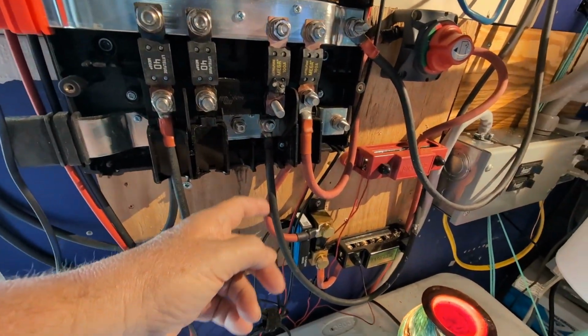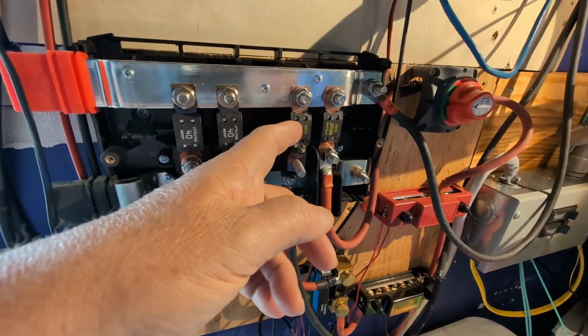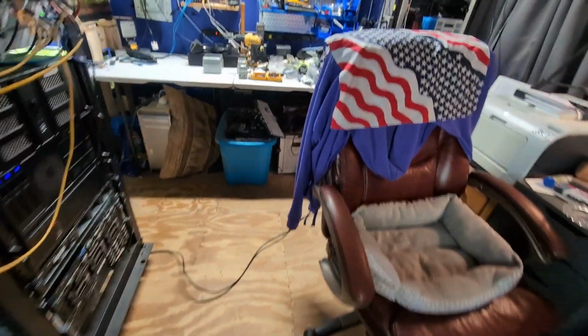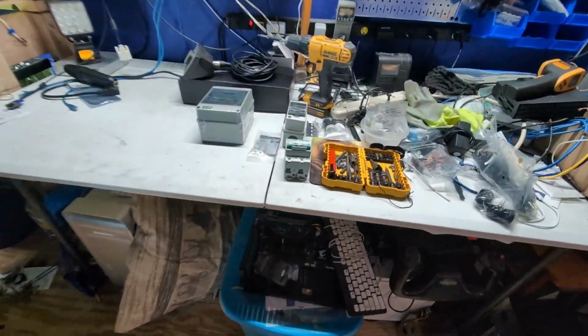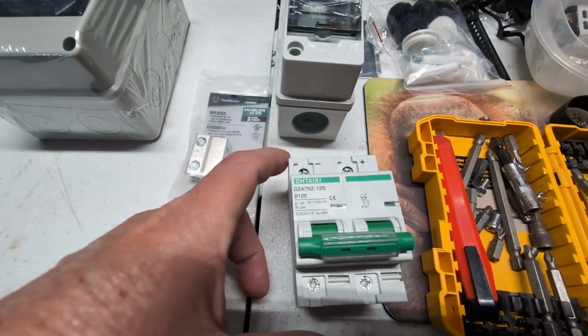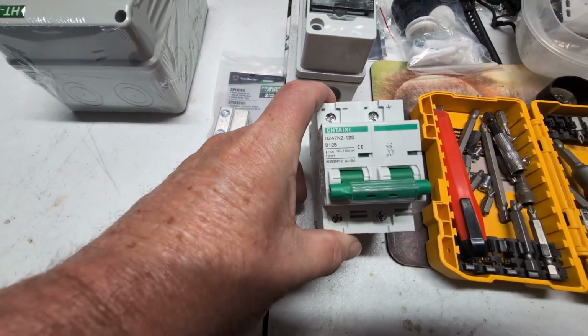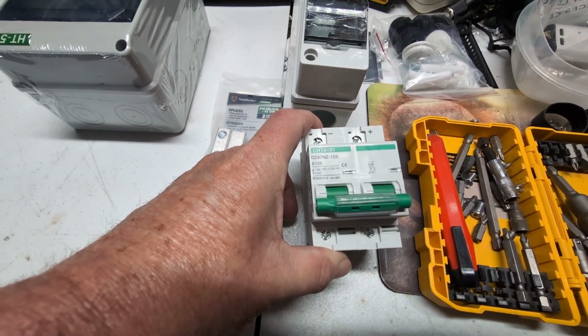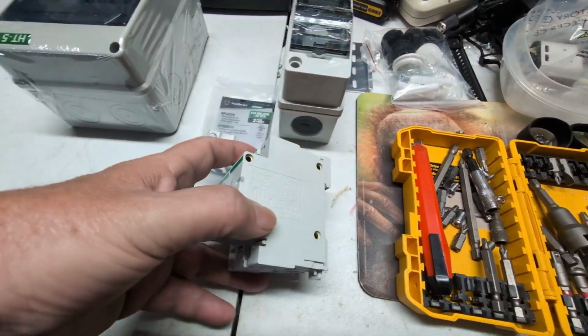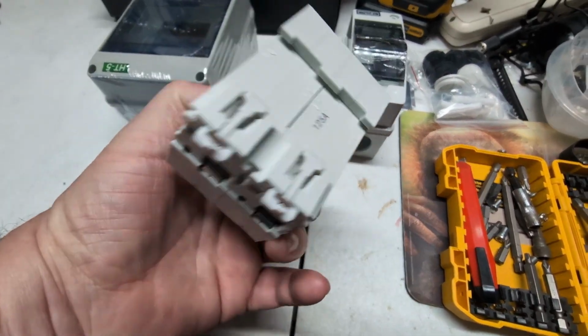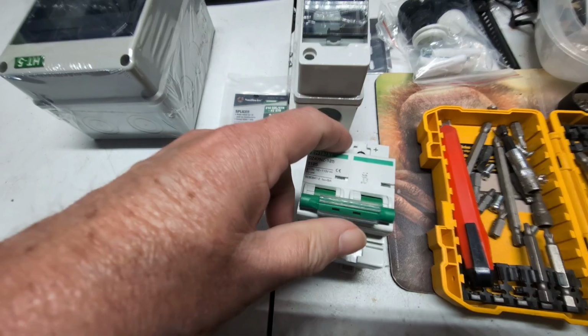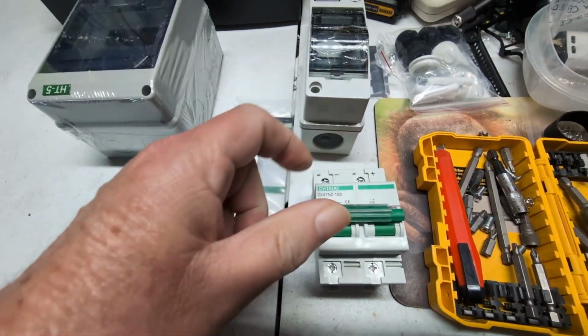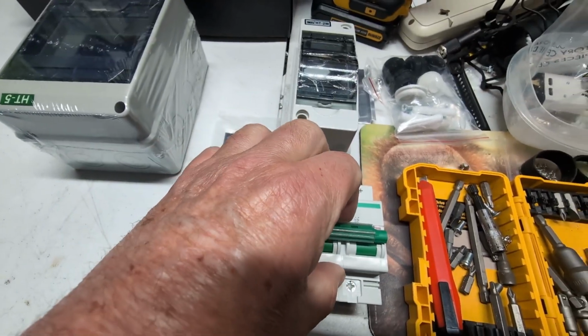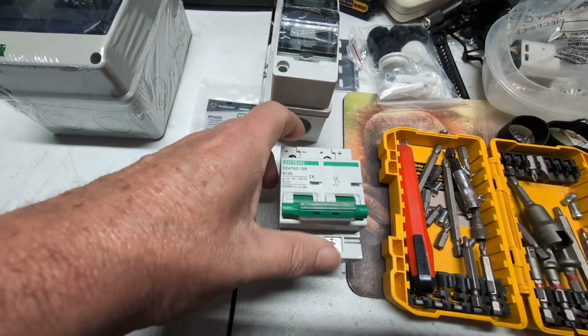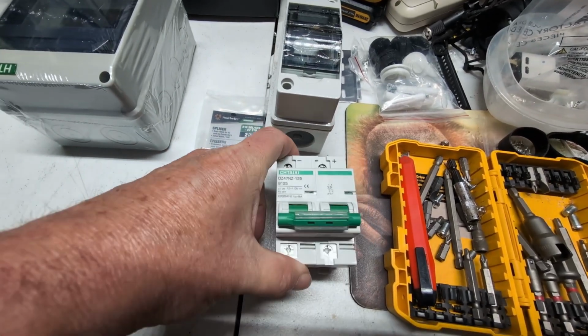Instead of the power coming through a fuse, we're going to go a little bit different, and we're going to run it through this breaker. This is a 125 amp DC rated breaker, and it also has arc fault or arc extinguishment, which you need on a DC circuit that you don't necessarily need on an AC. So it gives you a little bit of added protection.